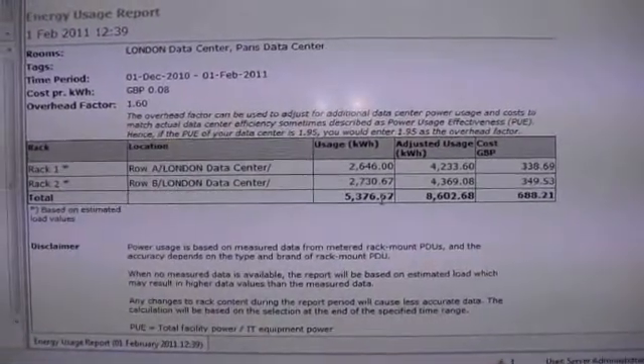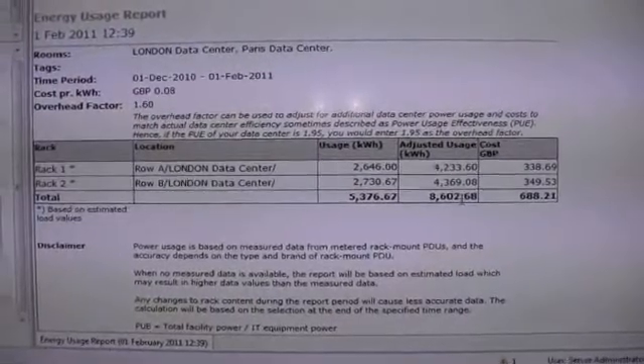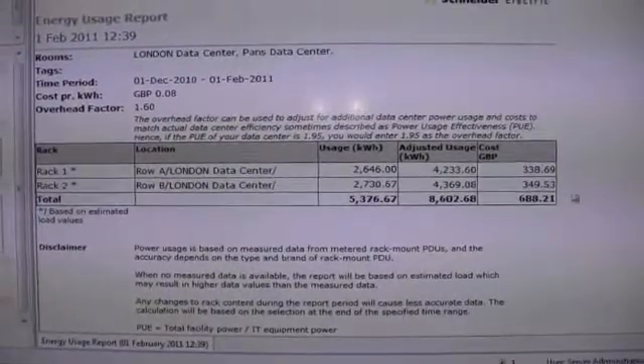The usage in kilowatts real time, the adjusted usage — which is your PUE factor, that's this figure times 1.6 — and the actual cost. So now you've got the ability to either talk to the customer about the billing, or talk to a department about why they're using these facilities at this cost and help reduce it, or maybe they need to use more, in which case you need to look at your infrastructure again to upgrade or increase your power, your cooling, or your rack densities. Thank you very much.